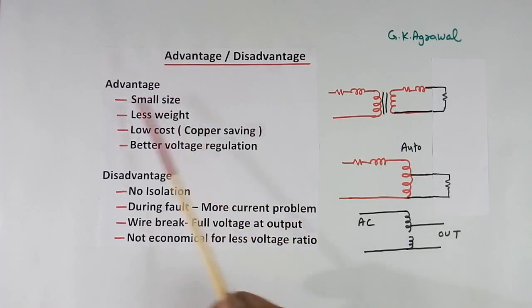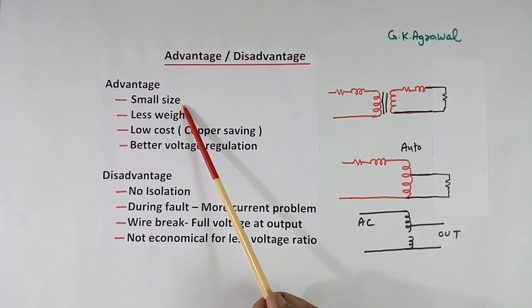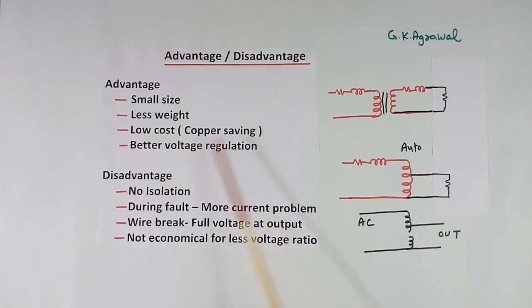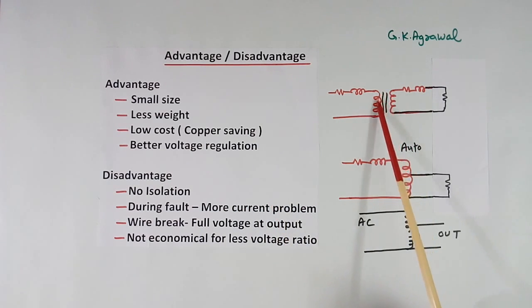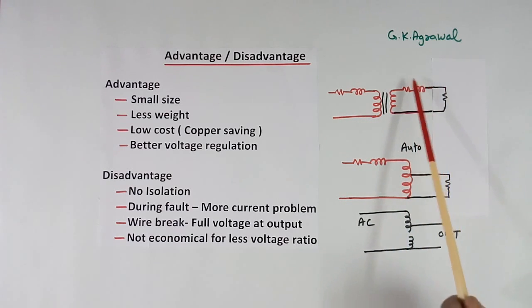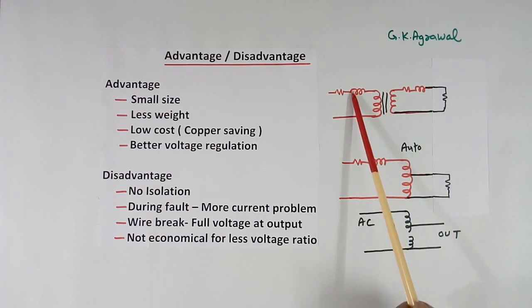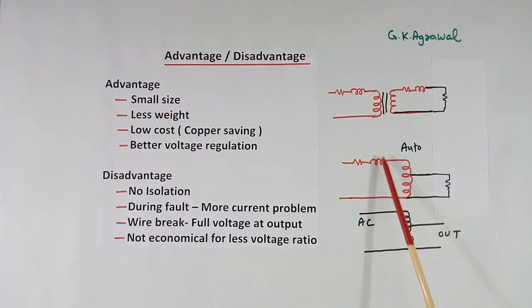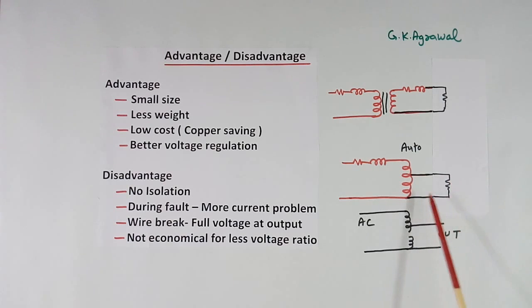Advantages: small size, because there is only 1 winding — so size, weight, and cost are less, and there is copper saving. Also, better voltage regulation. In a normal transformer, each of the 2 windings has its own impedance, so when load current flows there is a voltage drop across both. In an auto transformer there is only 1 winding with only 1 impedance, so there is less drop and better voltage regulation even when load current changes.